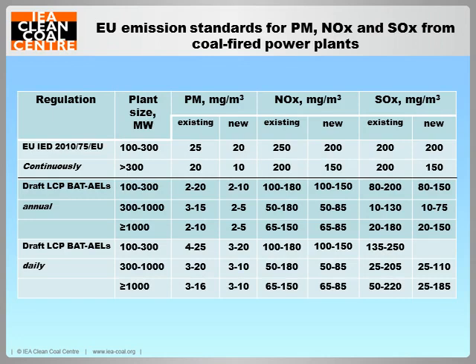This is the EU's emission standards for PM from coal-fired power plants. In the EU, coal-fired power plants are regulated by the Industrial Emission Directive, IED. This directive merged seven pieces of legislation, including the Large Combustion Plant, LCP, Directive. The binding emission limits in the IED are based on what best available technologies, or BAT, can achieve. BAT reference documents, termed BREFs, set up the BAT and their associated emission levels, shortened as BAT AELs, in the table.